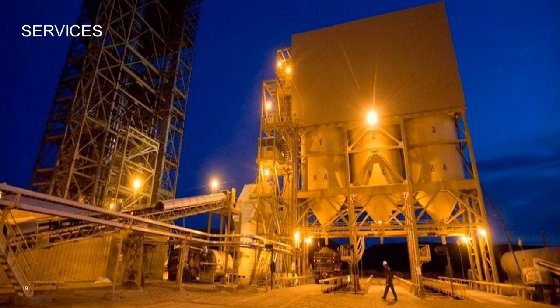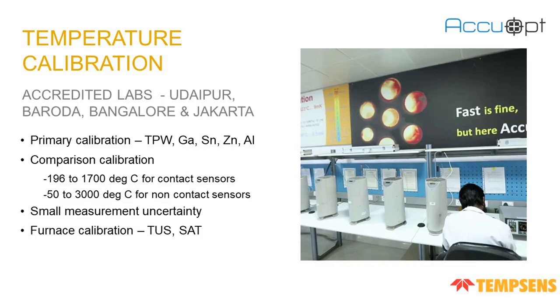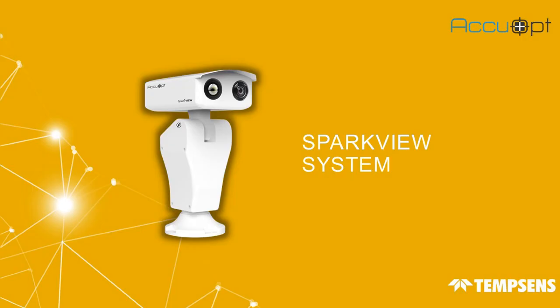and mats. These are the services which we provide: the temperature calibration lab. We have our own temperature calibration labs in Udaipur and Jakarta, with comparison calibration of minus 196 to 1600 degrees Celsius for contact sensors and minus 40 to 3000 degrees Celsius for non-contact sensors. We have our furnace calibration, TUS and SAT. Moving towards today's topic, which is the SparkView system, particularly dedicated to substation hotspot monitoring.